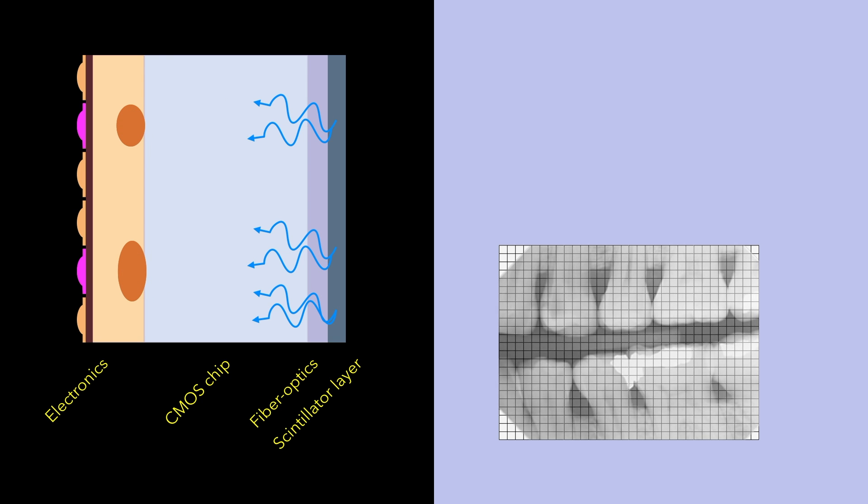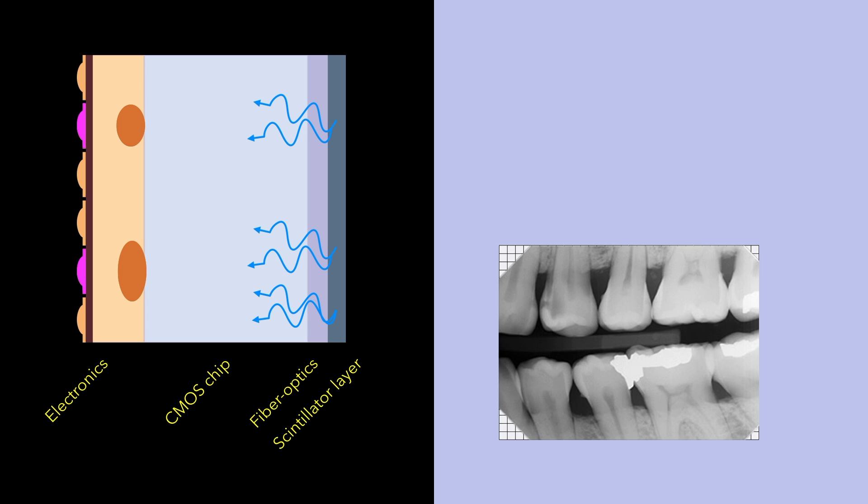So to summarize the process: X-ray photons strike the scintillation layer, producing light photons. The light photons interact with the semiconductor chip to produce electrons. The electrons then accumulate to form charged packets, creating a measurable voltage and a signal for image production.